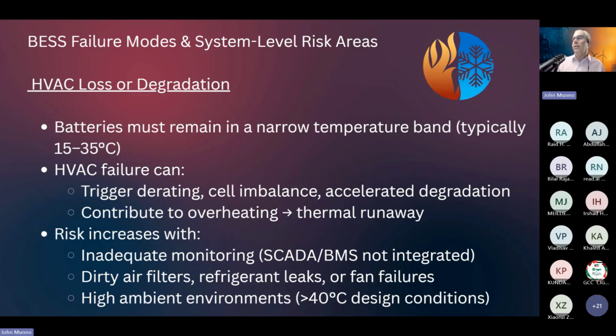And little things, I can't tell you how many sites I've been to where I've seen either dirty air filters or fans, the spare fans just laying on the floor, the ground, where you can tell they've been replaced. The maintenance, obviously, they go out and find failed fans. Well, guess what causes fans to fail? They fail when the air filters get clogged. And why would air filters get clogged? Especially if you're following the manufacturer's recommendation to replace the air filters every 6 months.